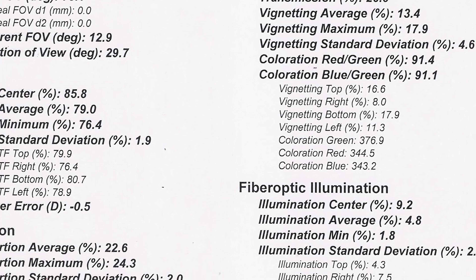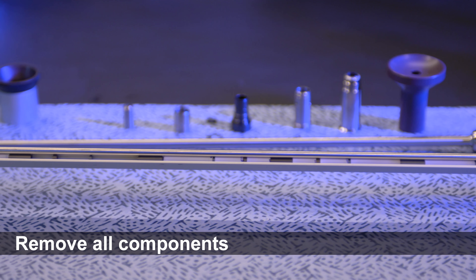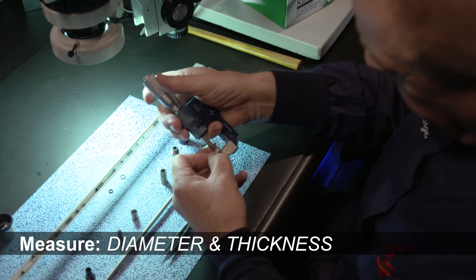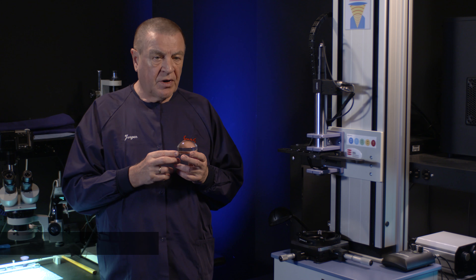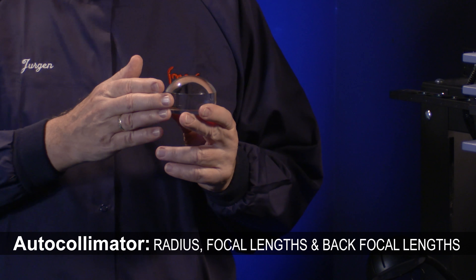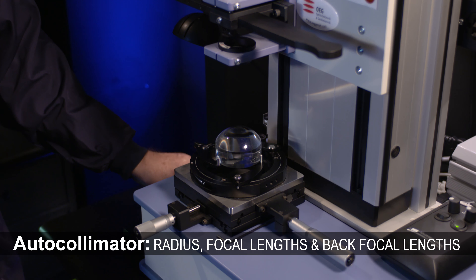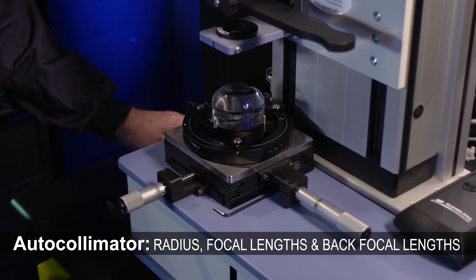The final printout is for us a guideline for how good the endoscope has to be when we return it to our customers. The next step is we take it apart, lay it out, take out all the components, and take basic measurements for diameter and thickness, but we also need to take more optics-specific parameters.